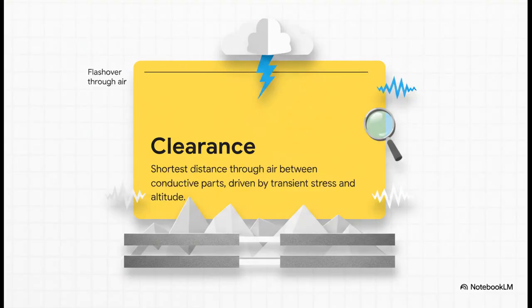Let's define them properly, starting with clearance. Clearance is the absolute shortest distance through the air between two conductive parts. Its one and only job is to prevent a flashover through the air during a sudden overvoltage event, like a lightning strike or a massive transient spike. Because it's an air gap, it's driven heavily by the rated impulse withstand voltage, or Uimp. And interestingly enough, it's also driven by altitude, which we'll get into a bit later. Essentially, it controls dielectric breakdown right through the air.